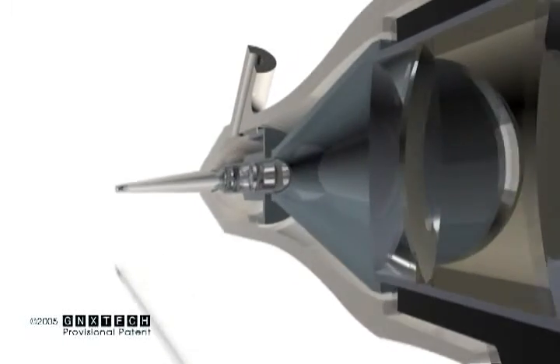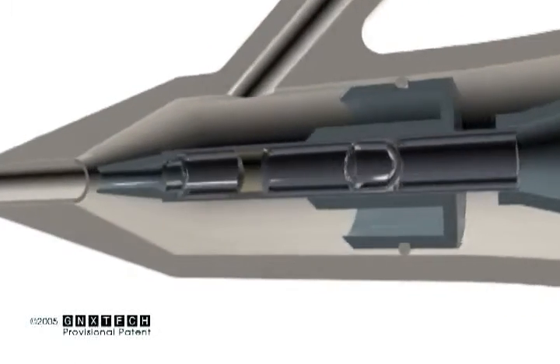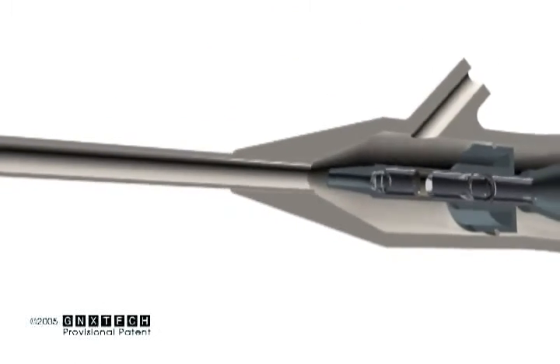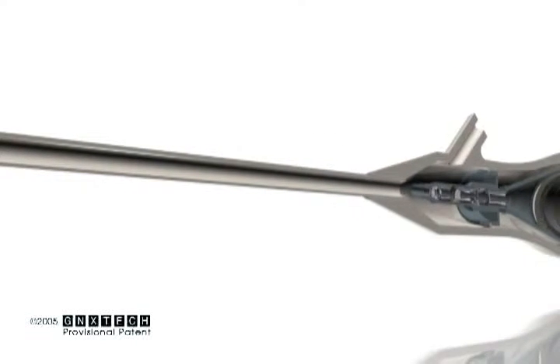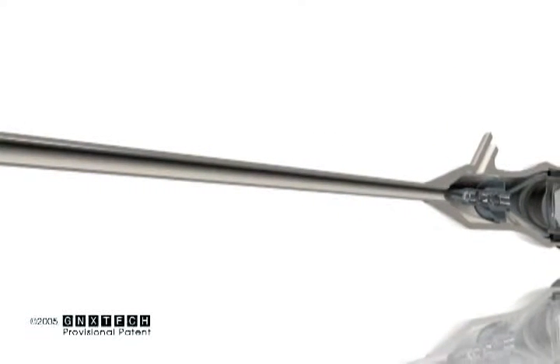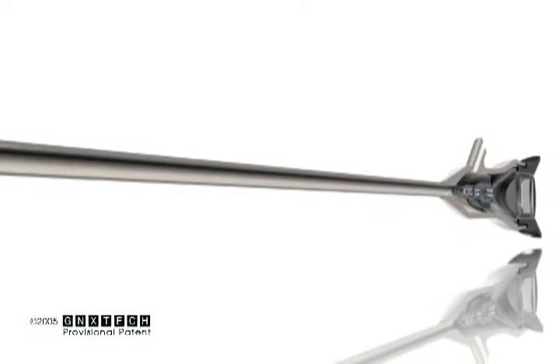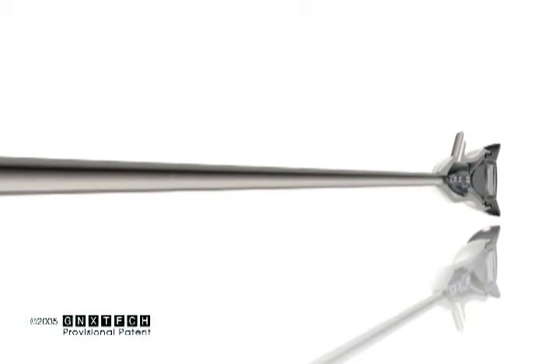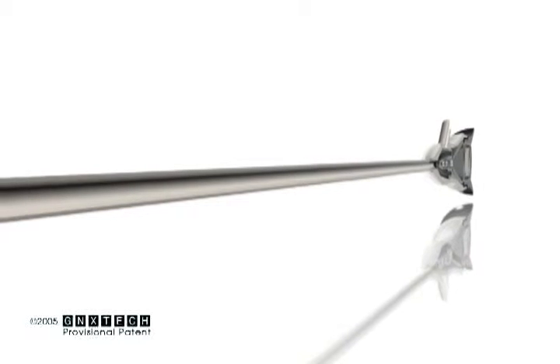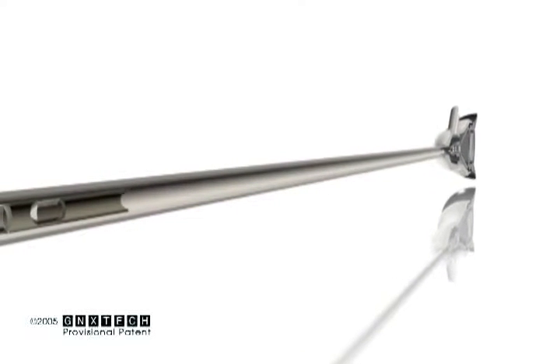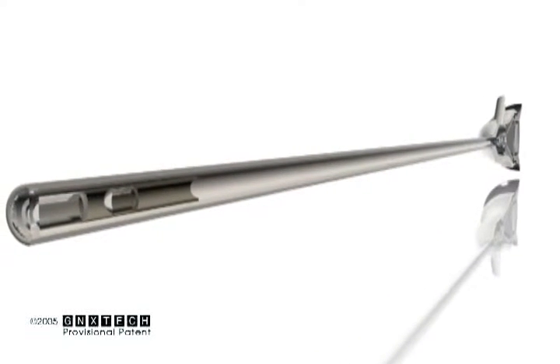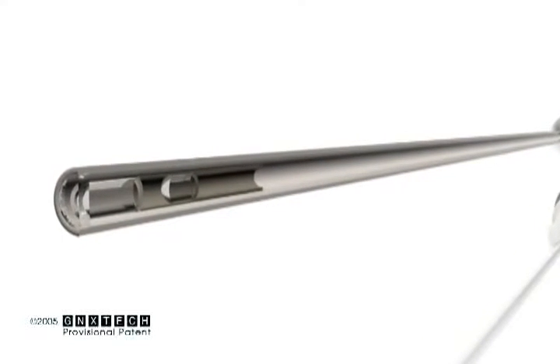This is the first endoscope designed to allow refocusing of the objective lens. This is important for changing focus during temperature shifts, when liquids contact the front surface of the lens. The front objective lens surface is flat, so no optical power change is expected. But bubbles may sometimes interfere, and some correction will be possible with this endoscope.